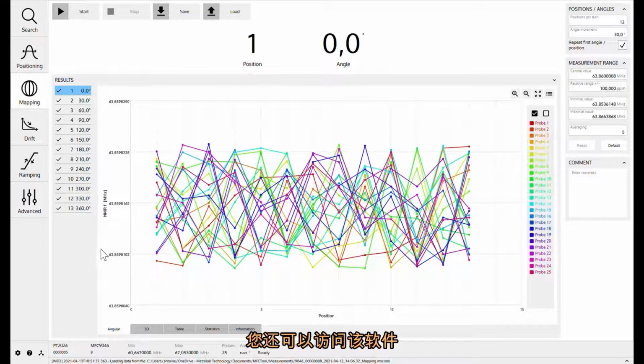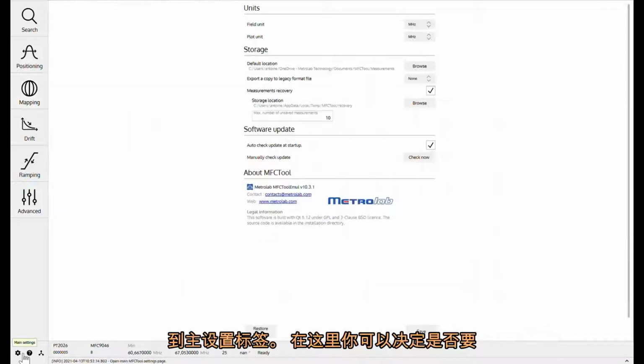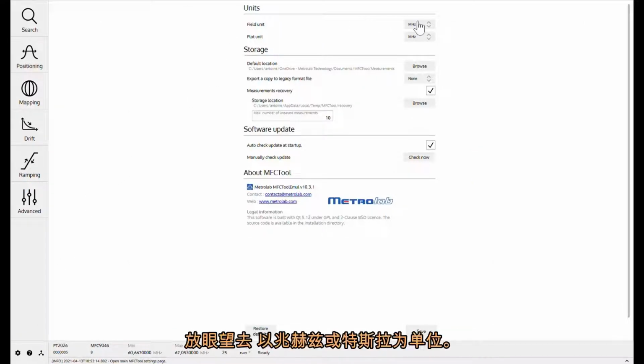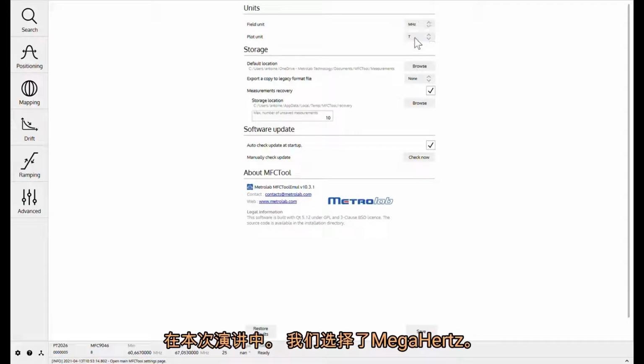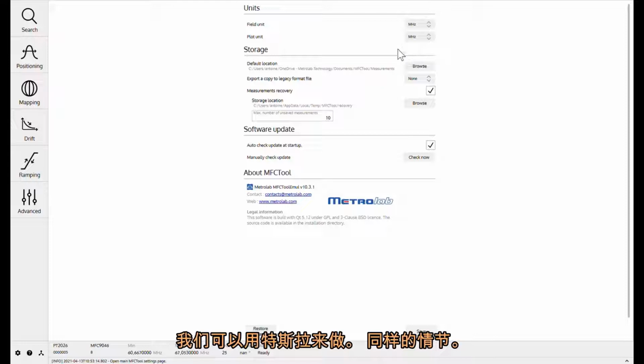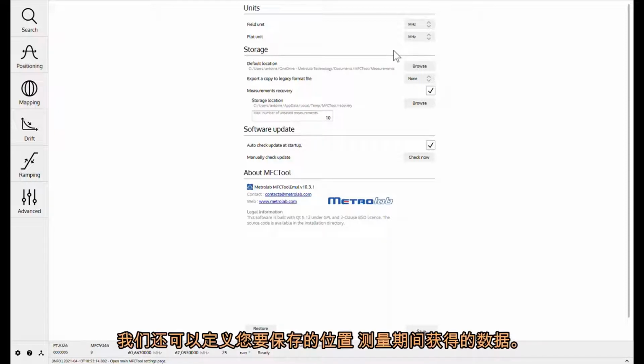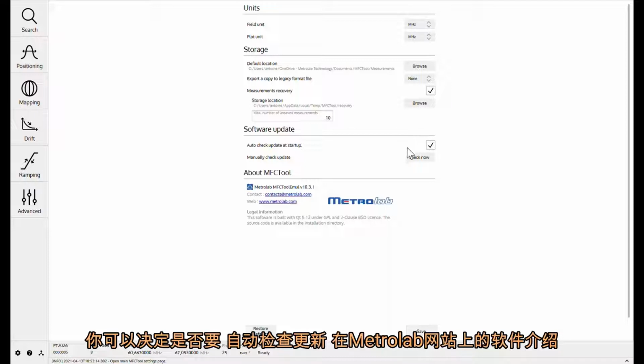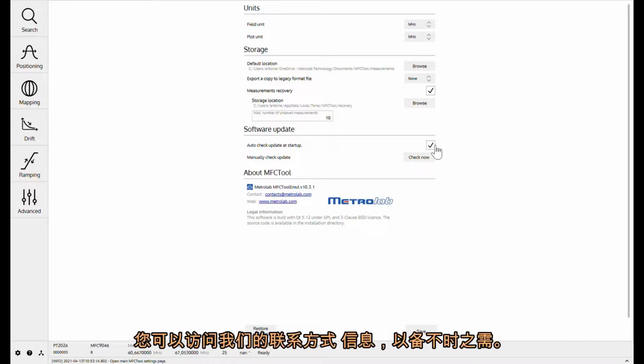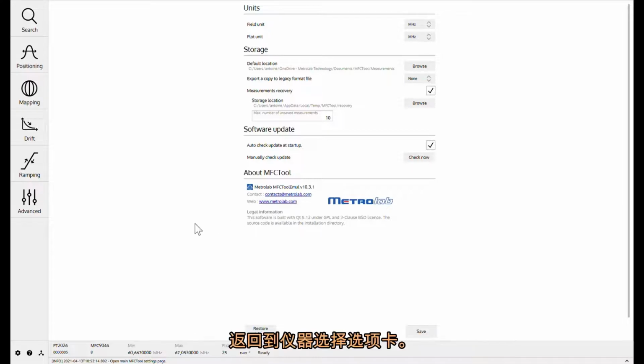You also have access on this software to the main setting tab, where you can decide whether you want to be looking at the field in megahertz or in Tesla. In this presentation, we have selected megahertz. We could have done it in Tesla. Same for the plotting. You can also define where you want to save the data acquired during the measurements. You can decide if you want to automatically check for an update of the software on Metrolab website, and you have access to our contact information in case you need it. To return to the instrument selection, click the icon at the bottom left of the screen.